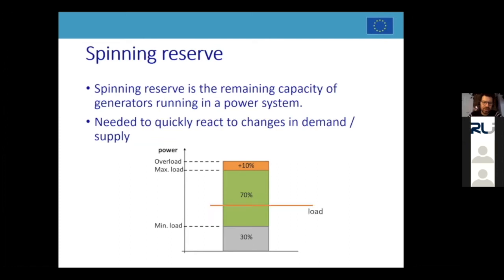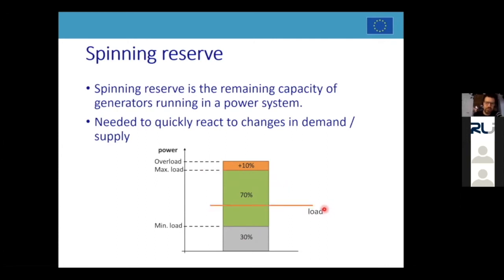And this is theoretical, but here we see a diesel generator, where basically the minimum load would be 30%, maximum load is 100%, and it can even go into overload for a certain time. So the green is the area you would usually operate it, and orange you can for a certain time, and gray you can't. If you run it below 30%, it would cause harm to the generator. And then here would be the load demand of the system. So it would be like at 50%. So the spinning reserve is what is left to be quickly provided by the generator.